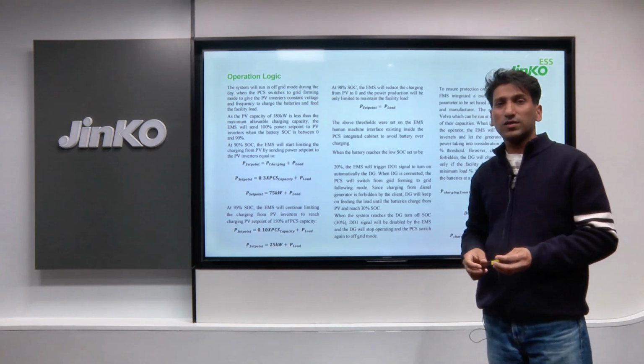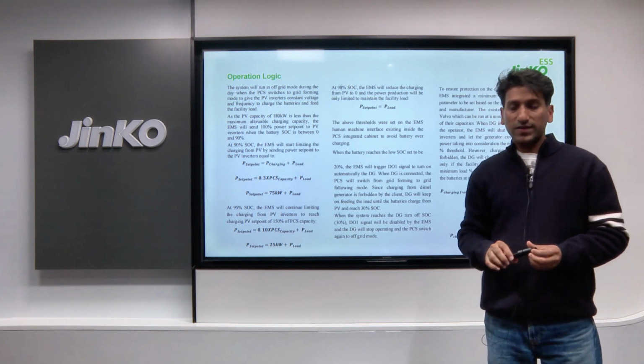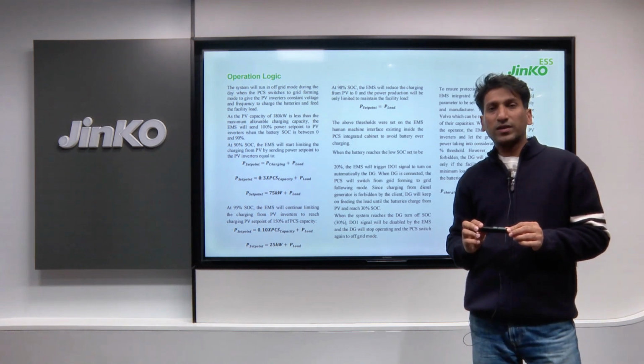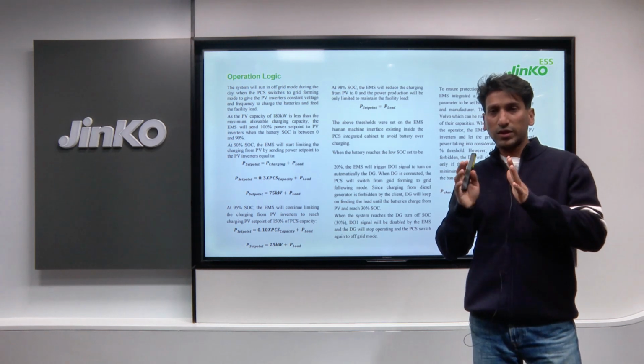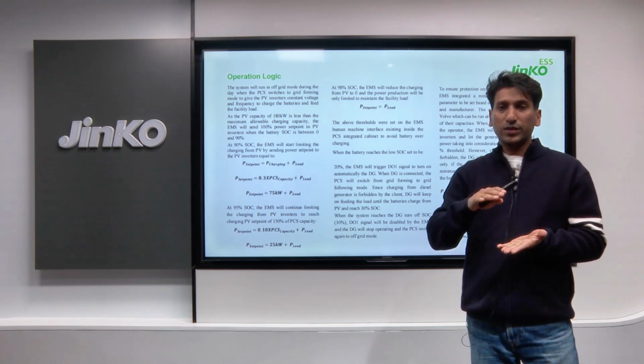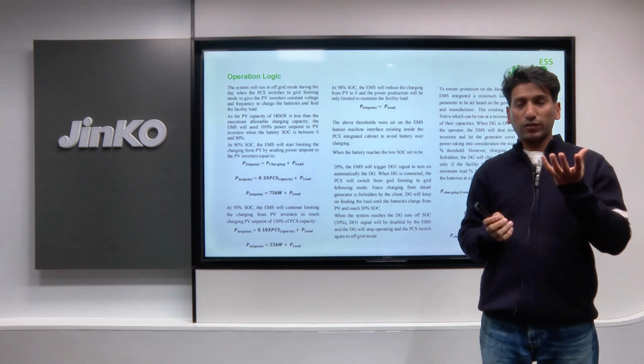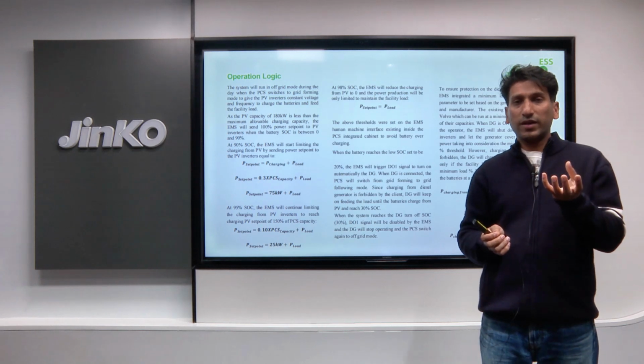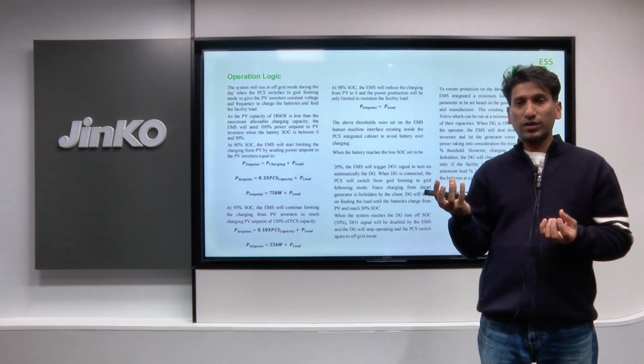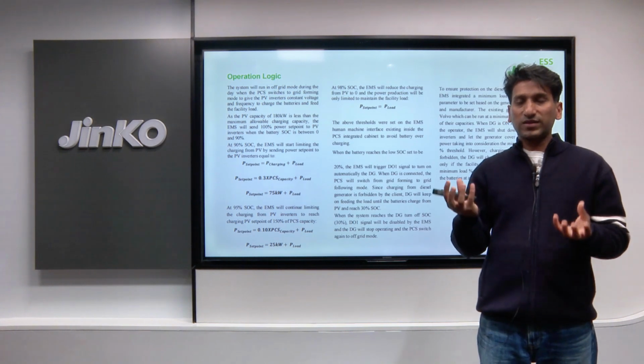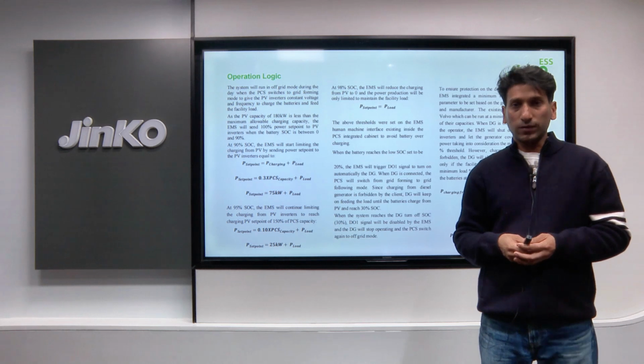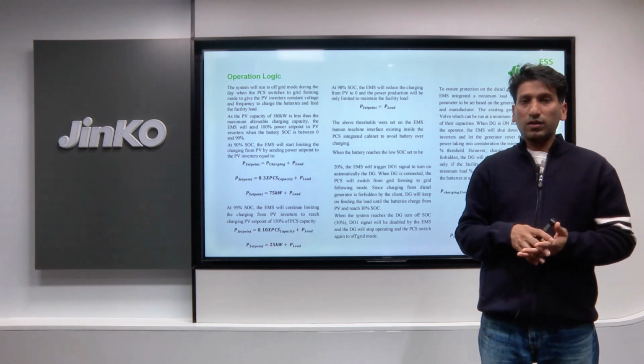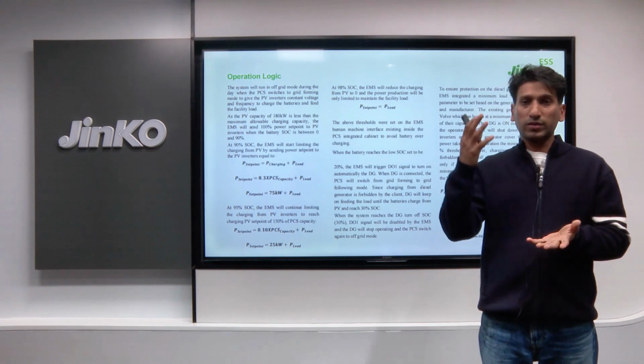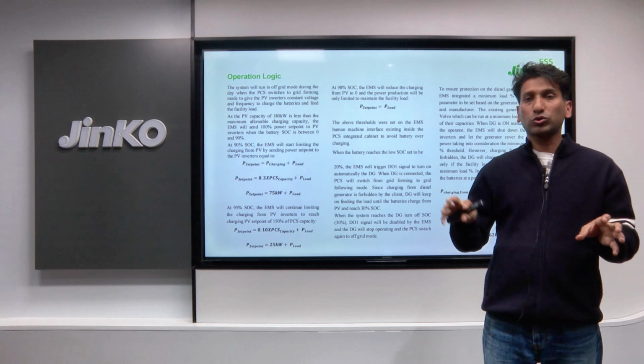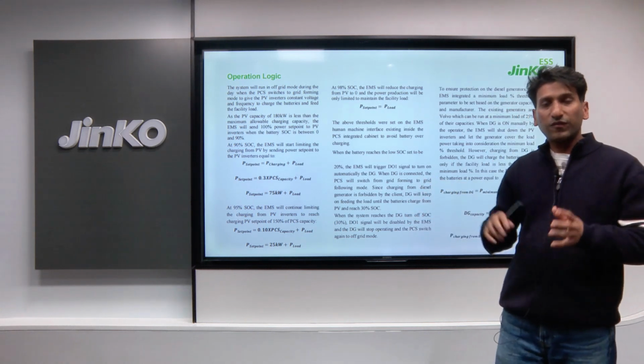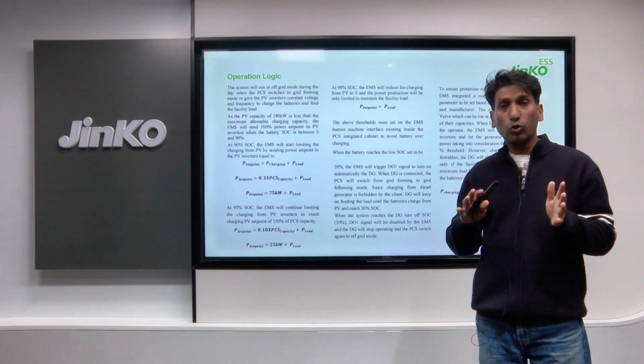For the operation logic of this site, we have set it in such a way that we look at the state of charge, the SOC, of the batteries. The PCS, the inverter on the battery side, is 215 kilowatt, and the PV inverter is 180 kilowatt. We have set it so that when the battery SOC is less than 90%, the PV inverter can supply all the power it can produce to charge the batteries and also to supply the load.